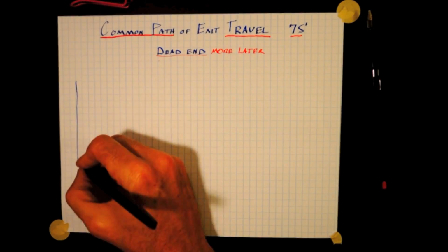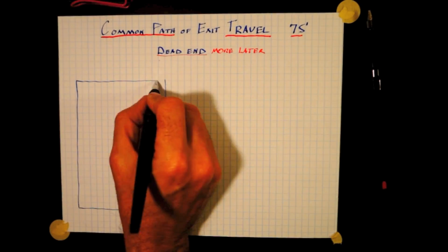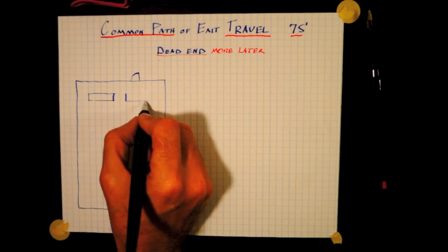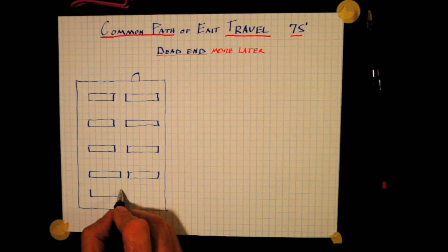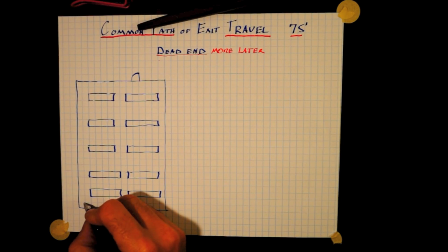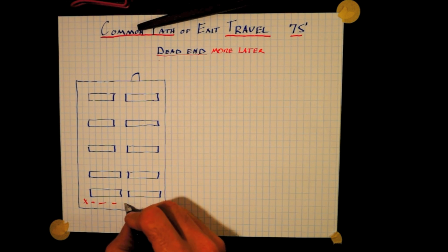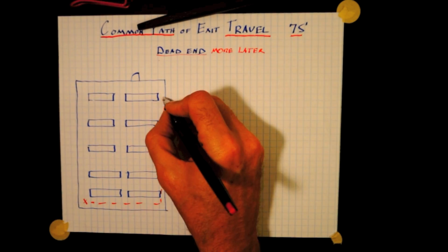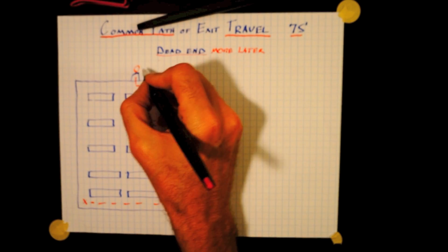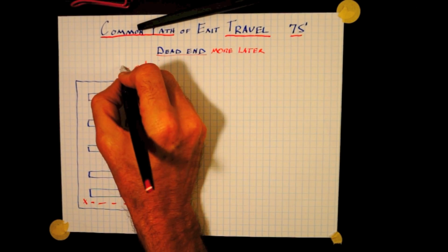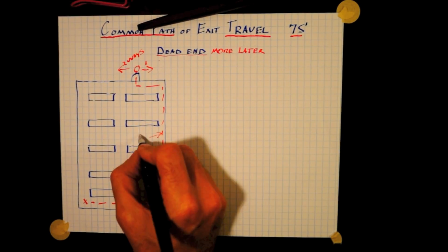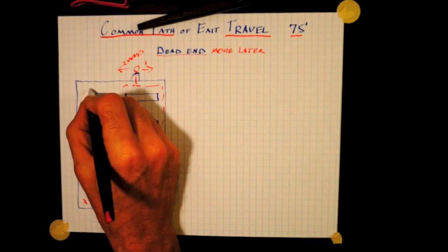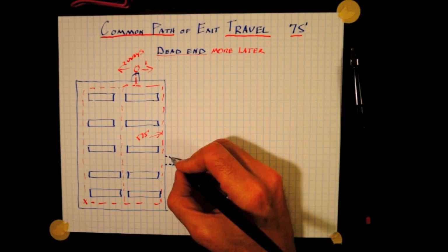Here we have a building, a room, with either office furniture, library stacks, or some object that we have to navigate around. Standing in the far corner, traveling to the exit, i.e. one door, we must reach a way to have two choices within 75 feet.